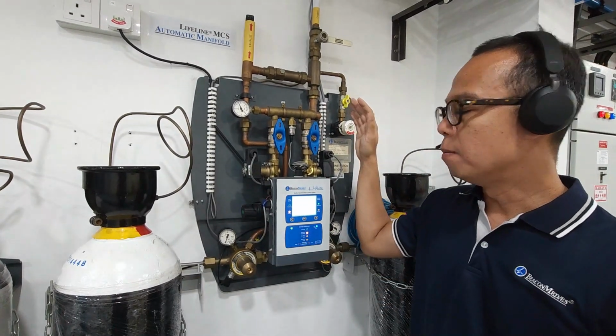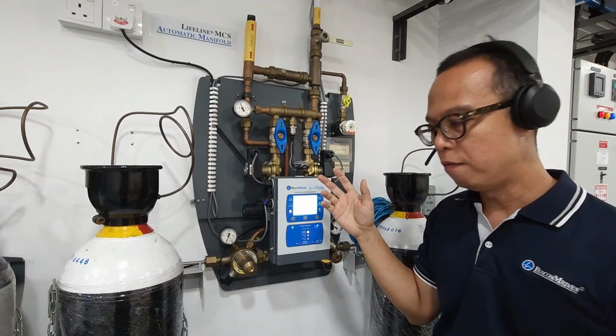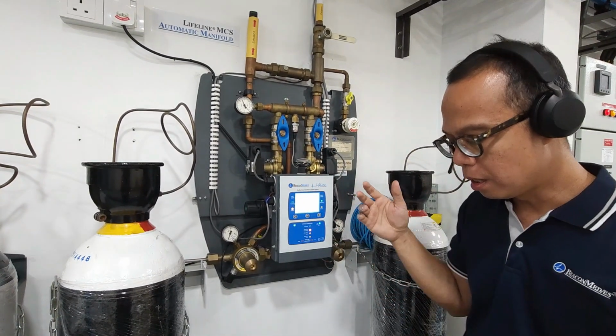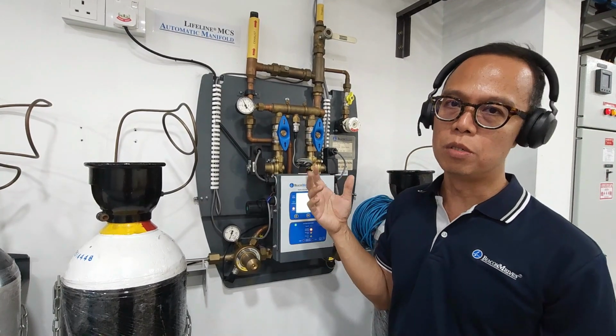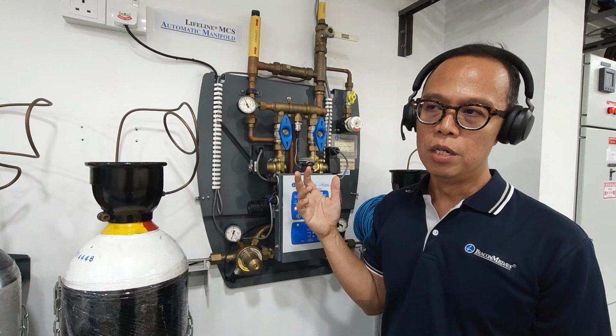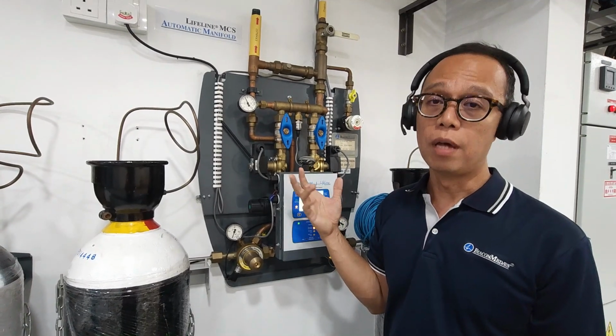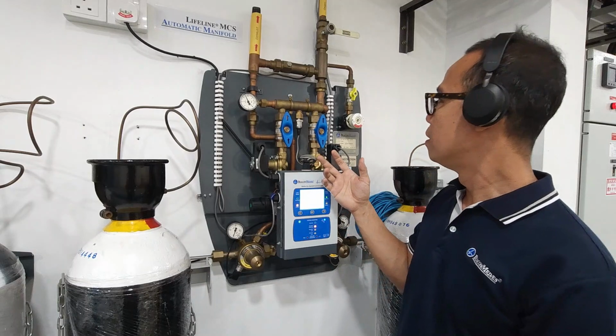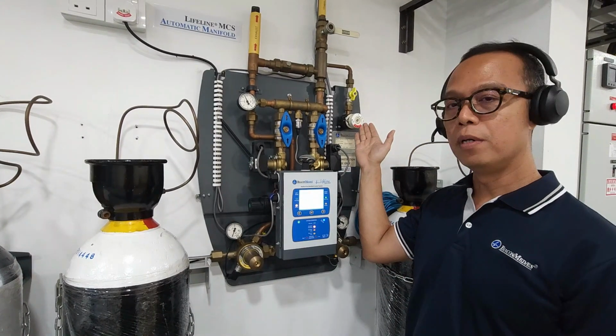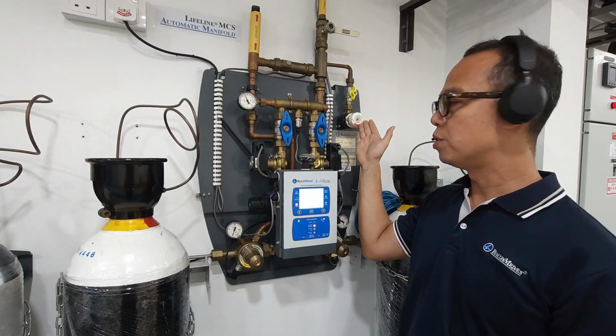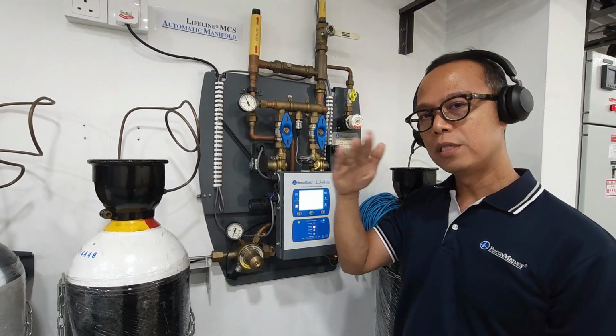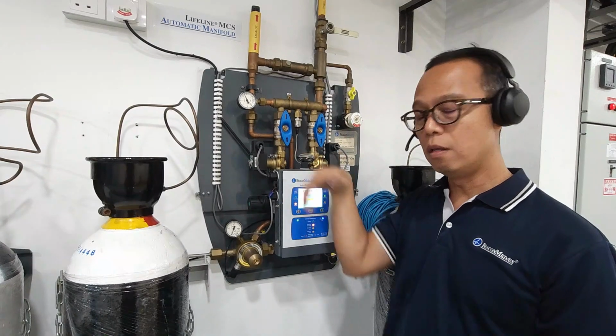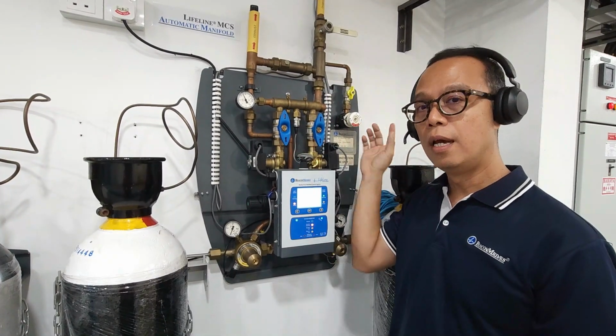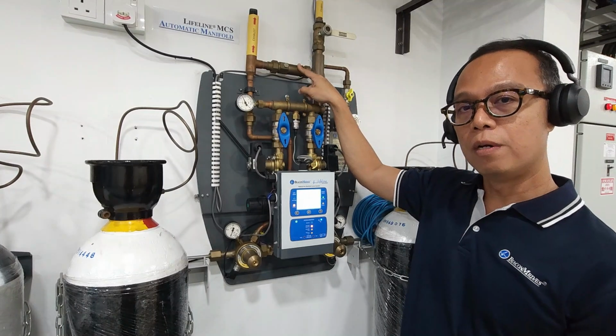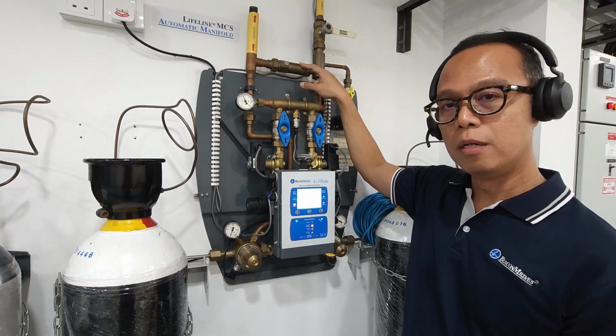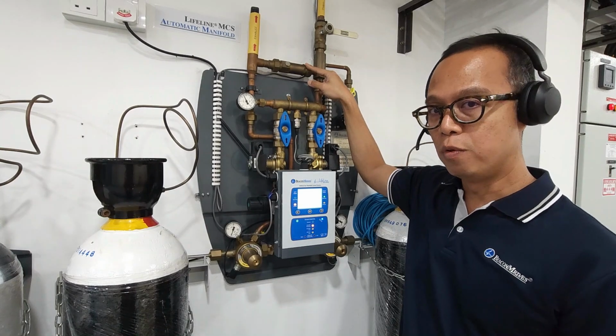The most important thing about this Lifeline manifold is we use non-halogenated components to make sure that no fire occurs with high compression gases. Each of the manifolds comes with a built-in terminal unit test point. This is an oxygen terminal unit, and for 4 bar, 7 bar, 11 bar, most of the equipment is the same except for the terminal unit, and also the safety relief valve up here is different for the 4 bar or 7 bar manifold.